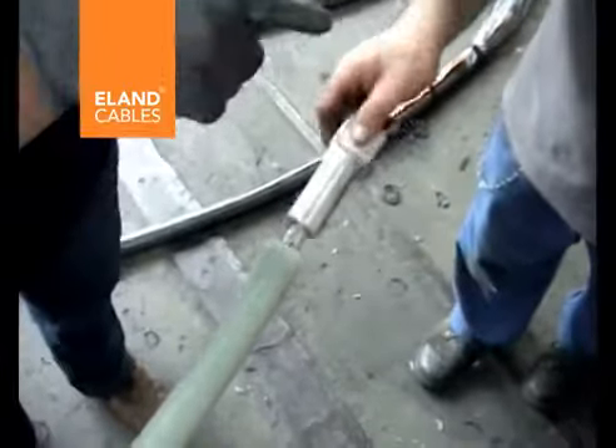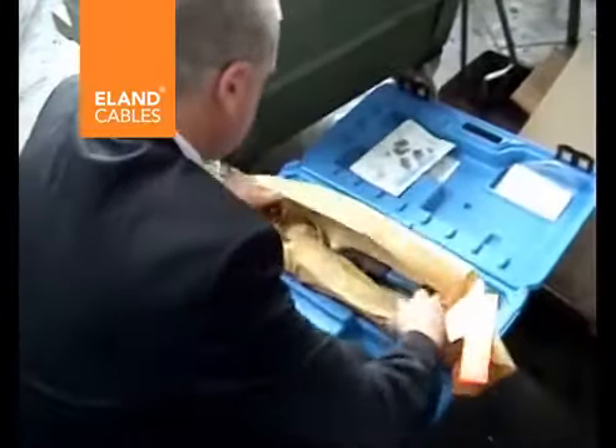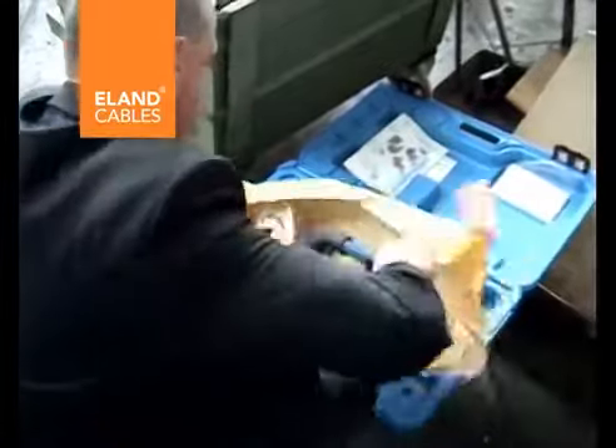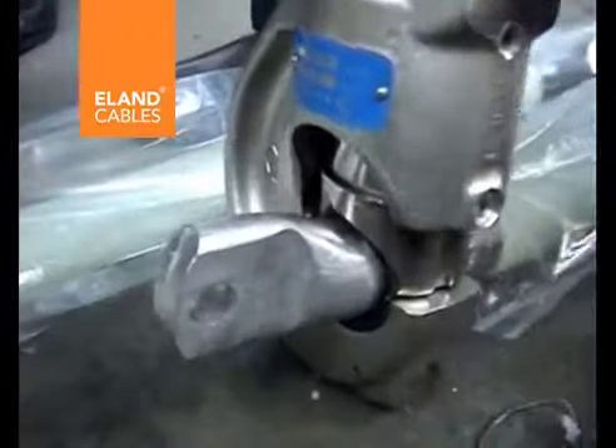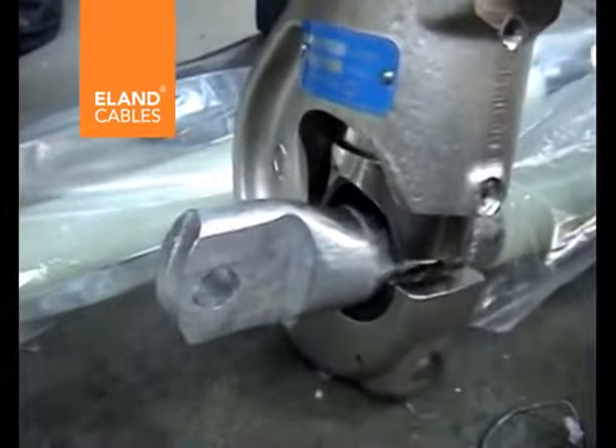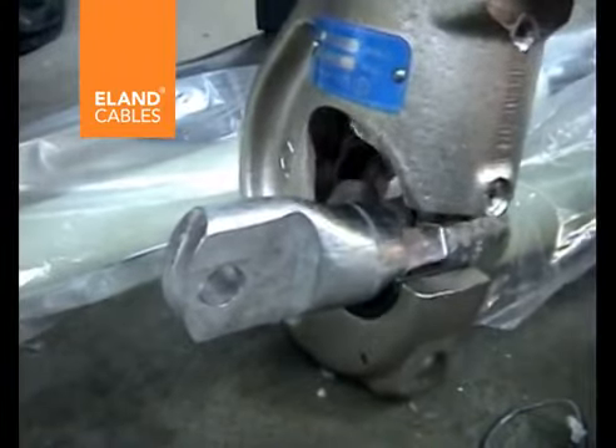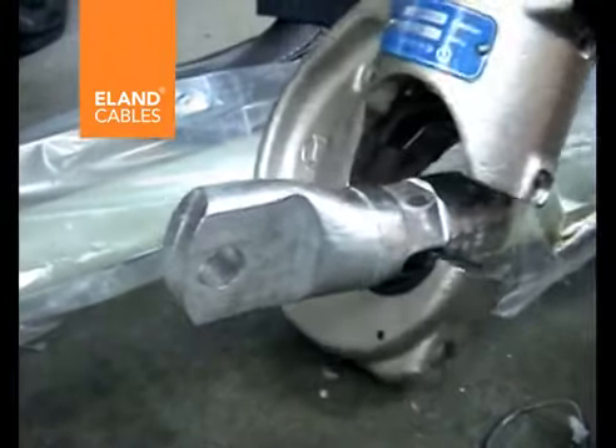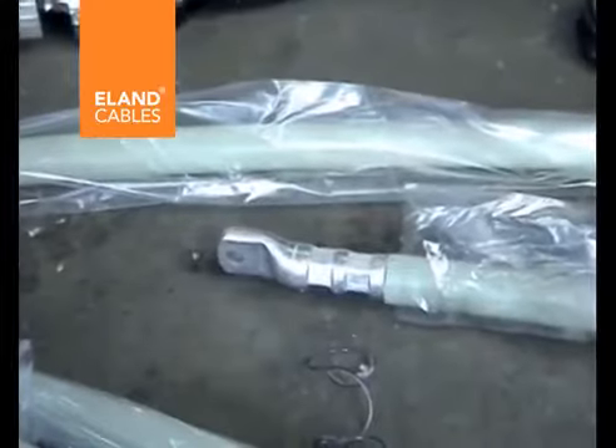A lug was fitted to the end and then crimped in place using a newly calibrated hydraulic crimping tool, which was fitted with inserts of the correct size. This ensured that the lug was securely attached to the cable. The cable was now fully prepared and ready for testing.